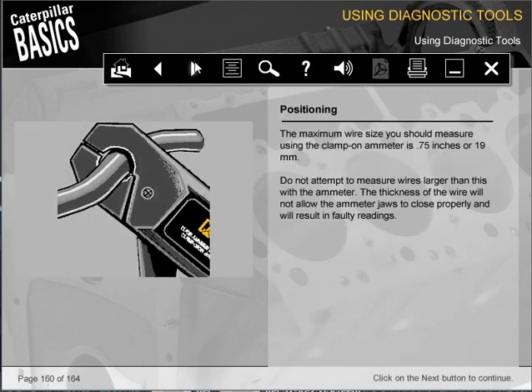The maximum wire size you should measure using the clamp-on ammeter is 0.75 inches, or 19 millimeters. Do not attempt to measure wires larger than this with the ammeter. The thickness of the wire will not allow the ammeter jaws to close properly and will result in faulty readings.